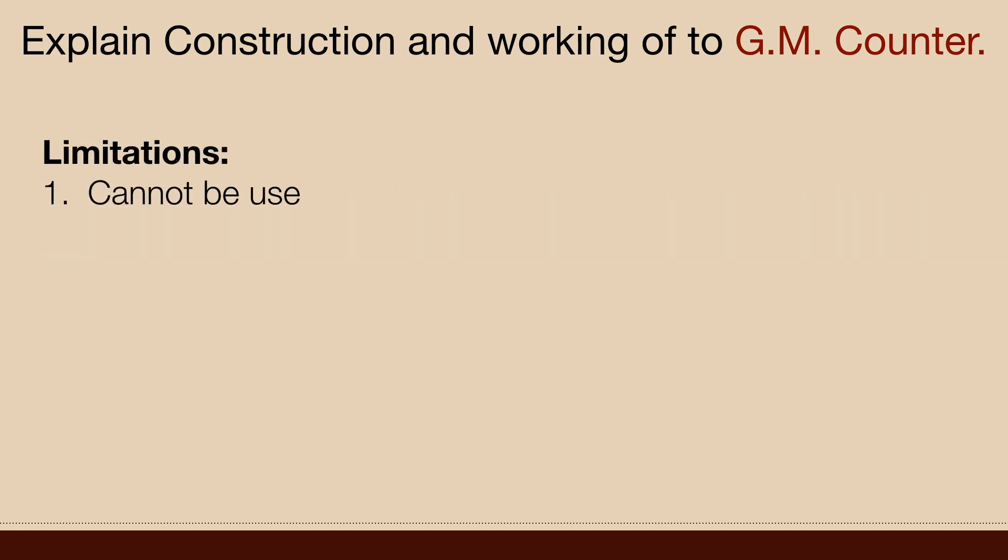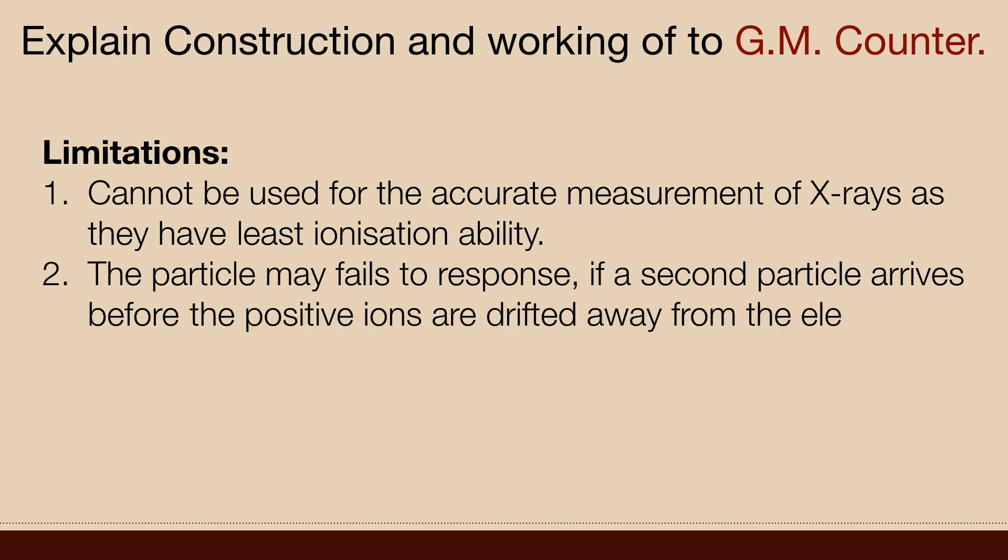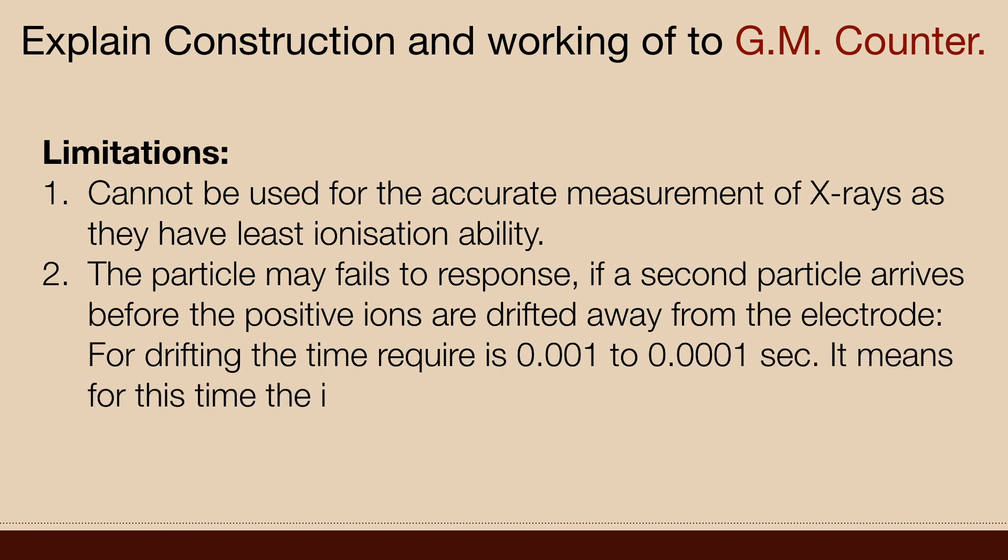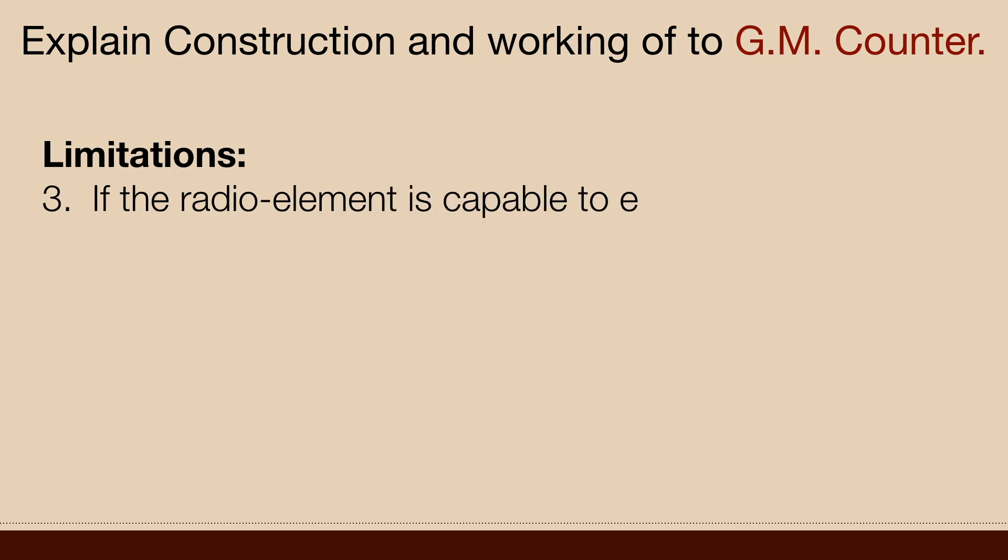Limitations: It cannot be used for accurate measurement of X-rays as they have least ionization ability. The particles may fail to respond if a second particle arrives before the positive ions are drifted away from the electrode. For drifting, the time required is 0.001 to 0.0001 seconds. This means for this time the instrument is not giving any response. The above time is known as dead time for the instrument.